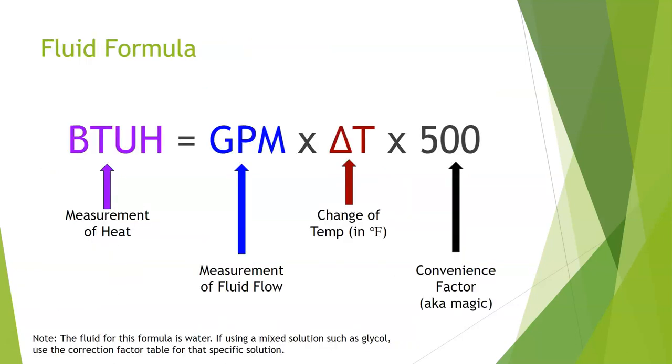Let's take a look at our fluid formula. If you watched my HVAC airflow calculation video, this is going to look shockingly familiar because it is the same formula with different variables. BTUH, a measurement of heat, equals GPM, a measurement of fluid flow, times delta T, change in temperature, times 500, which is our convenience factor or magic number. Air and water have different properties. Heat transfers through air different than water. That's where this 500 number comes in. Trust me, 500 is the magic number.